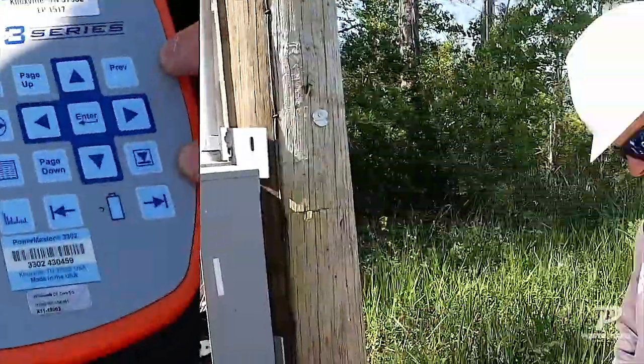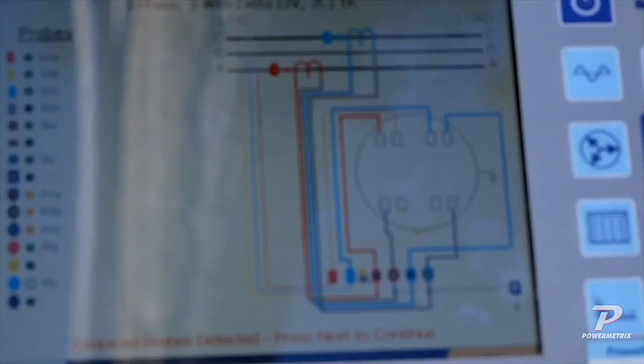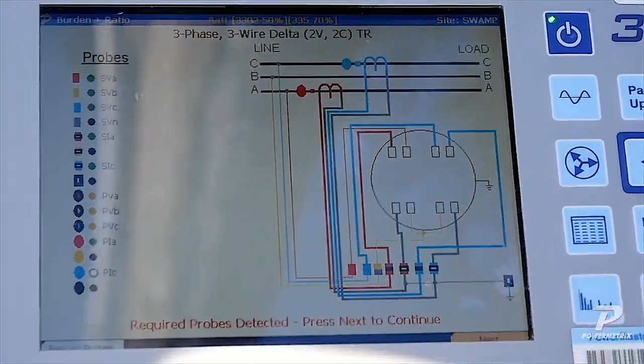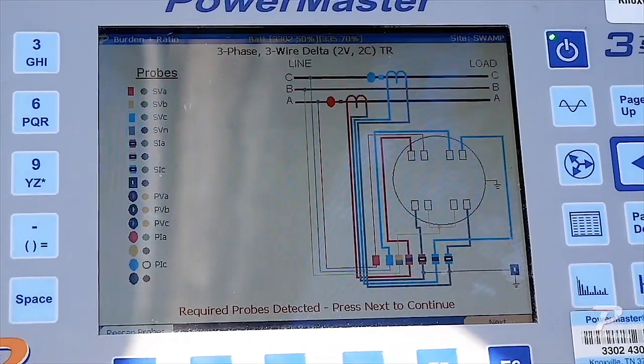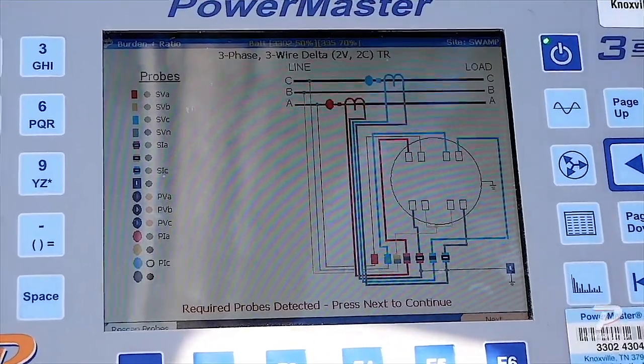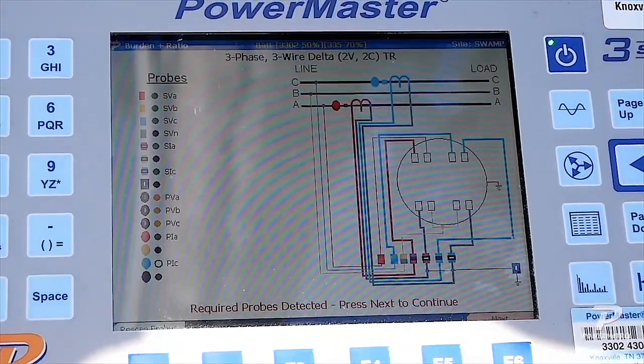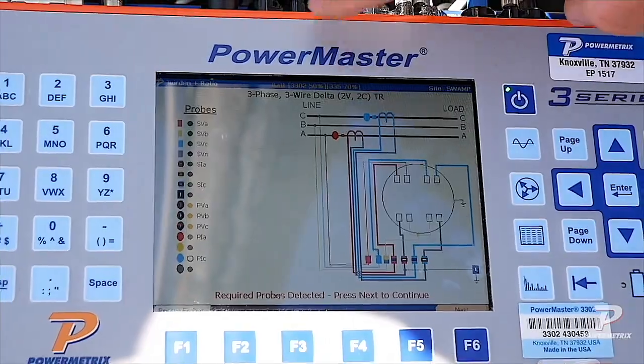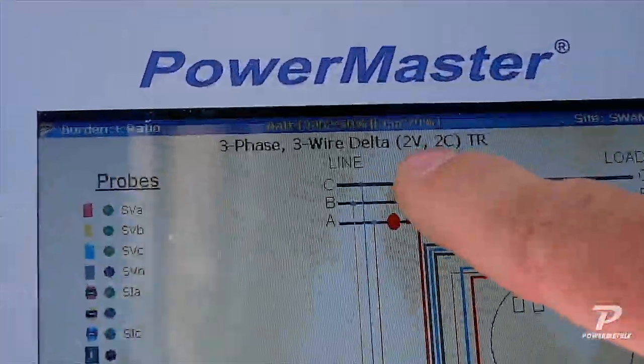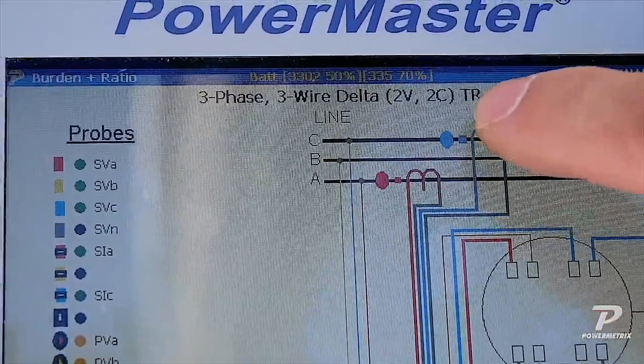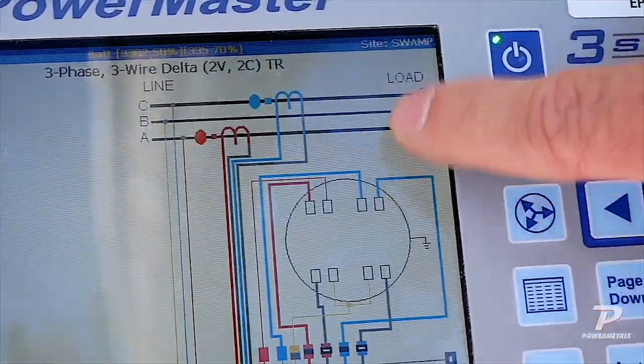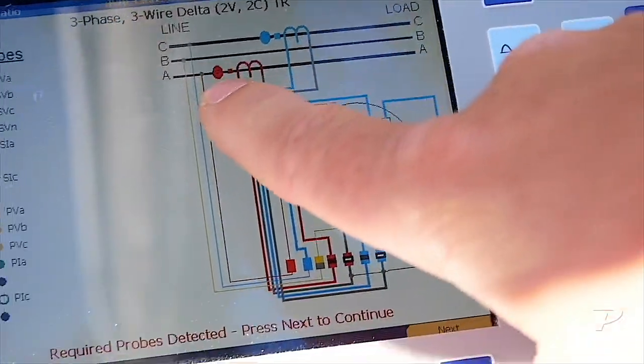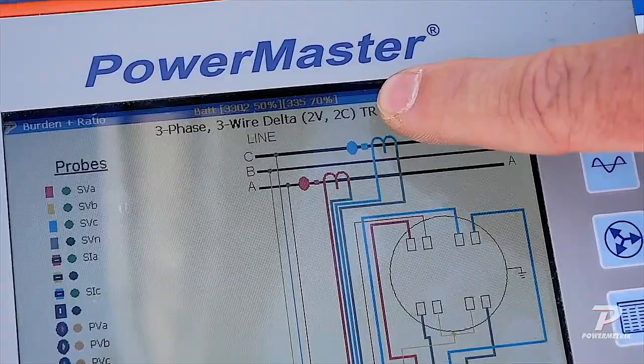Okay, so I've gone in and edited our site and changed our service type. Remember before we were on 4-wire delta, 2 voltage, 2 currents, 3 primary currents, and we had to change it to use our high volt probe on our stick. Now what I've selected is just a 3-wire delta because it's got 2 voltages and more importantly 2 currents. On our line diagram we just need 1 probe for A and 1 probe for B or C.